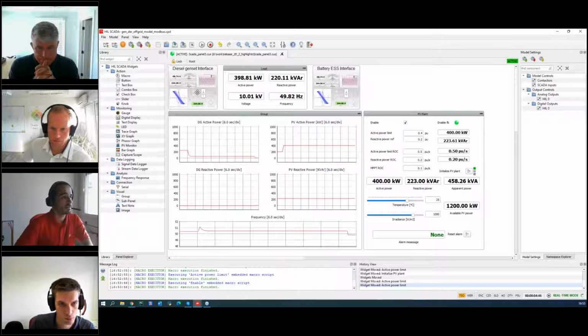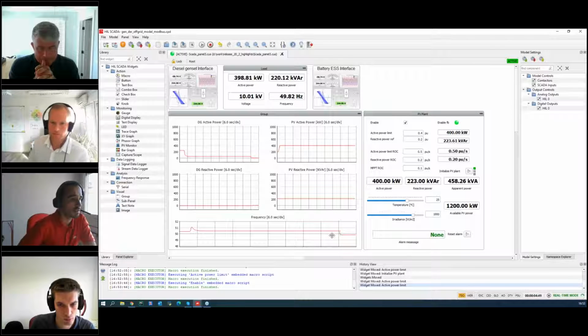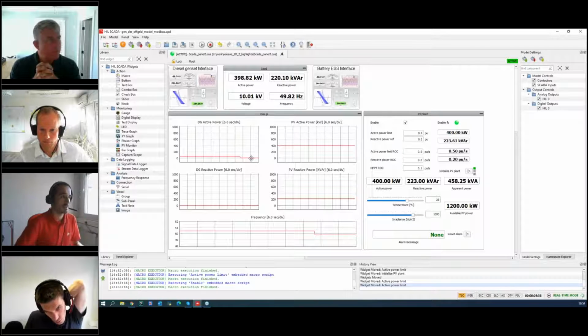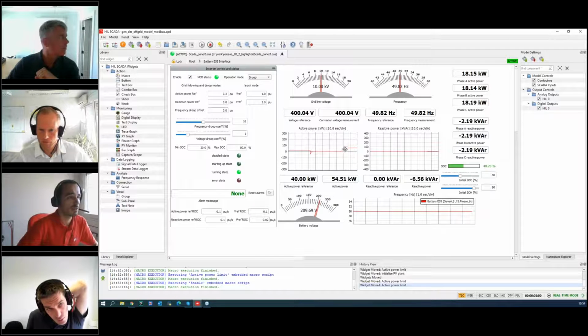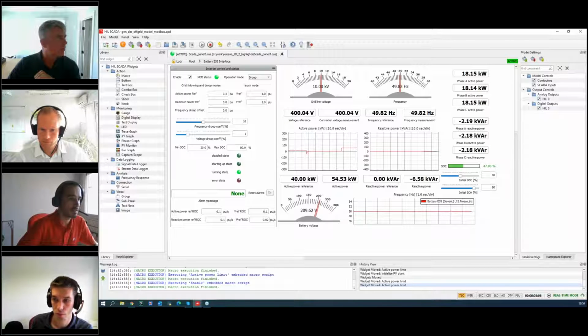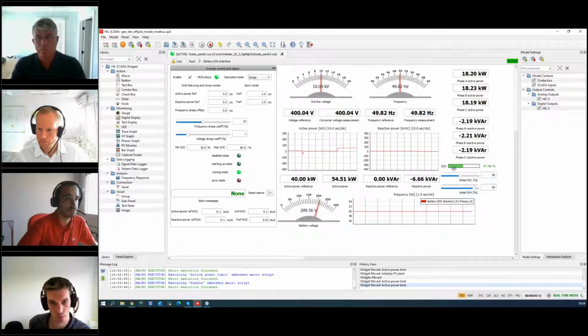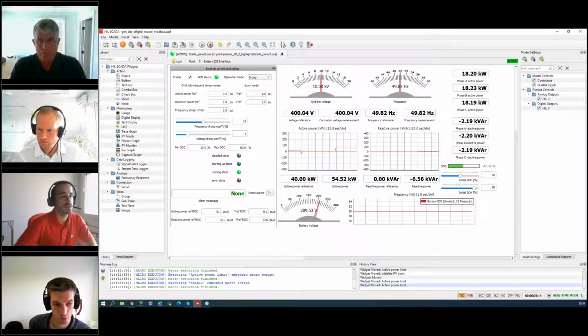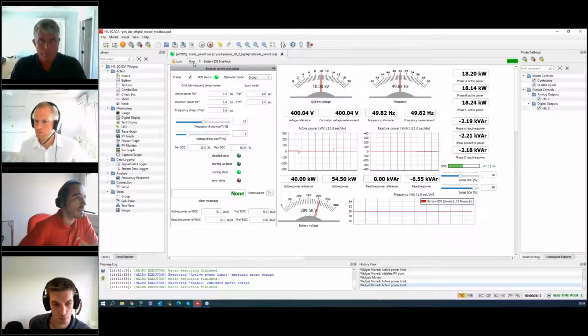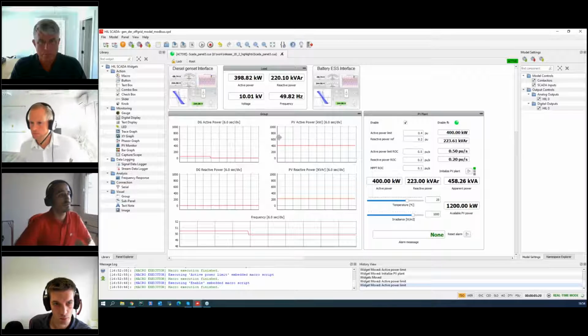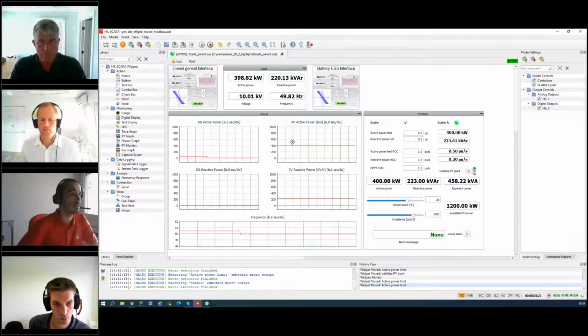Okay, I've done that. We can see in the system that our frequency dropped below 50 Hertz. The diesel genset active power dropped to 0. That's expected because we turned it off, and that means our battery took over that power to supply the load, and that is actually the case. Right now our battery is discharging. You can see here how the state of charge goes down. That's fine. Now we actually have a system where a battery and PV are supplying the load, and the diesel genset is not working.